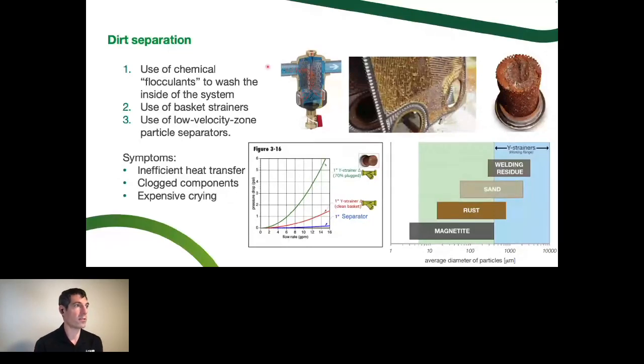So the difference with a dirt separator is it's a collision media, that same collision media that we talked about before, where the debris is going to hit and fall down to the bottom. The bell of a dirt separator is really important. You can take some cost out of those devices and make them smaller, but you want a low velocity zone here so stuff hits and falls down to the bottom. So now if I had 10 GPM and we've got two cups of dirt at the bottom of this thing, it doesn't affect the pressure drop going through that device.